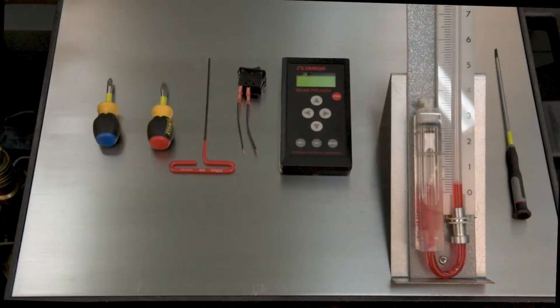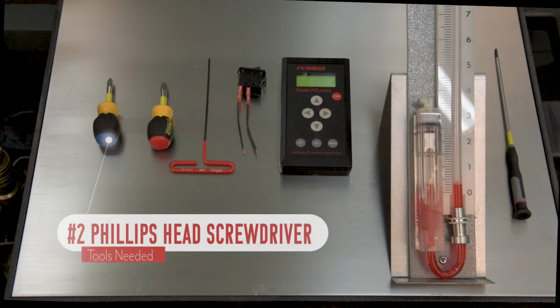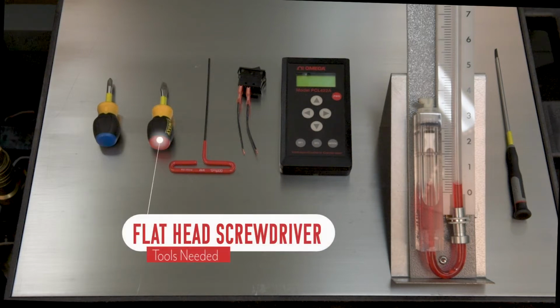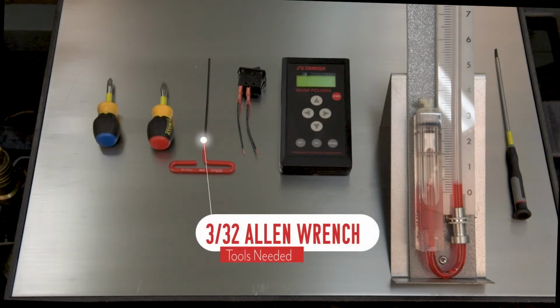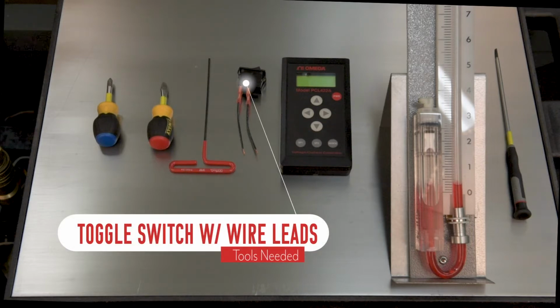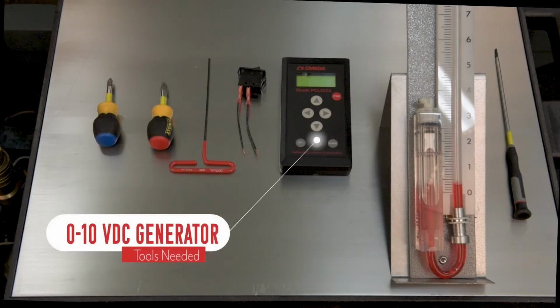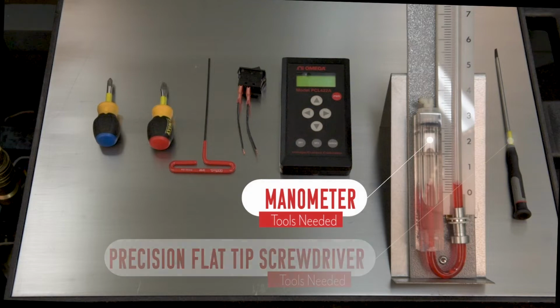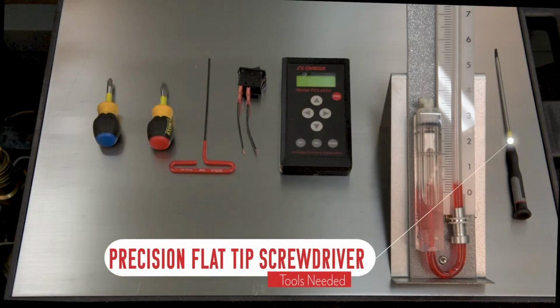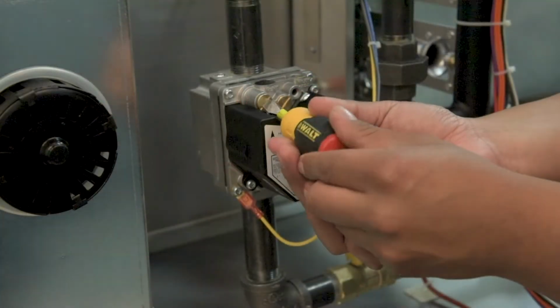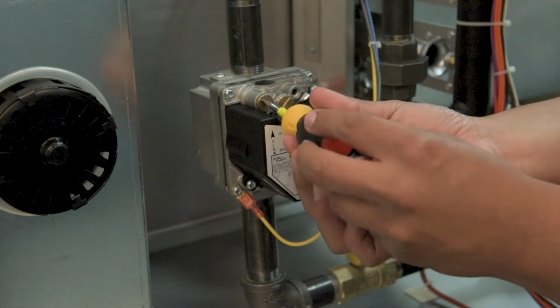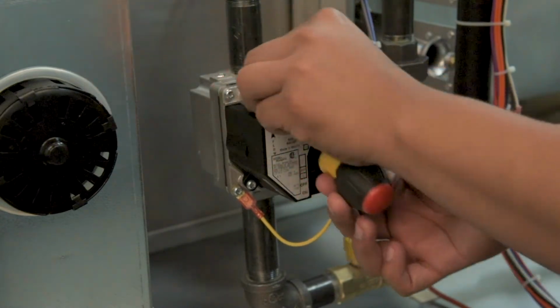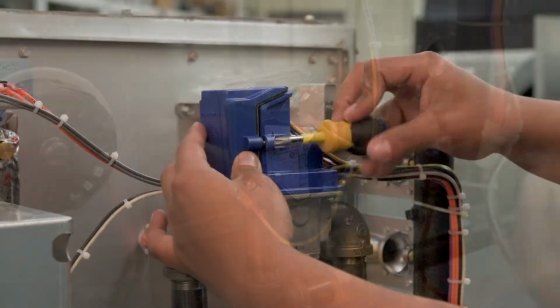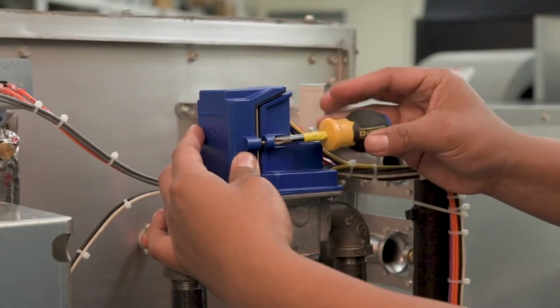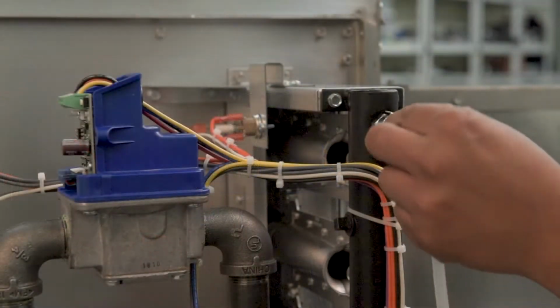These are the tools you will need to complete the test fire: a number 2 Phillips head screwdriver, a flathead screwdriver, a 3/32 Allen wrench, a toggle switch with wire leads, a 0 to 10 volt DC generator, a manometer, and a precision flat tip screwdriver.